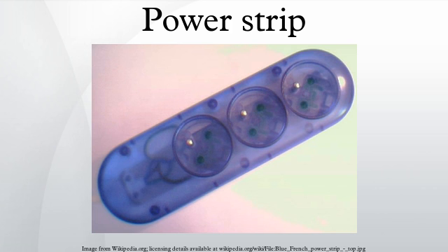Power strips are generally considered a safer alternative to double adapters, two-way plugs, three-way plugs, or cube taps, which plug directly into the socket with no lead for multiple appliances. These low-cost adapters are generally not fused. Therefore, in many cases the only protection against overload is the branch circuit fuse, which may well have a rating higher than the adapter. The weight of the plugs pulling on the adapter can also be an issue if adapters are stacked or if they are used with brick-style power supplies. Such adapters, while still available, have largely fallen out of use in some countries.